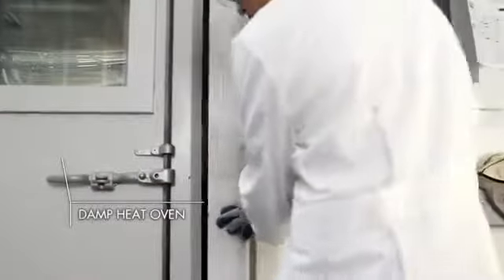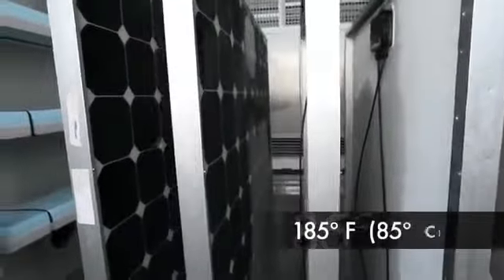This is a damp heat oven, designed to simulate real-world humidity for over two and a half decades. Inside, panels are subjected to 85% humidity at 185 degrees Fahrenheit.